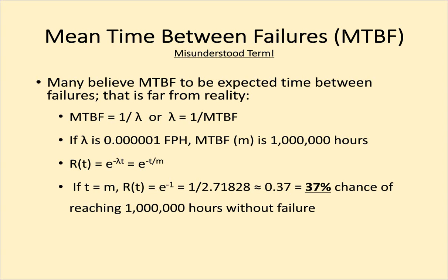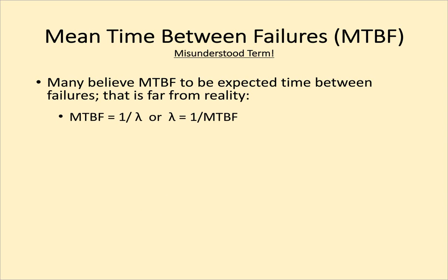Okay, so mean time between failure, again, as I indicated, is a misunderstood term. Mean time between failure is equal to 1 over lambda, and I defined lambda earlier. That's the failure rate over a given period of time. So lambda, based on math, is equal to 1 over MTBF as well.